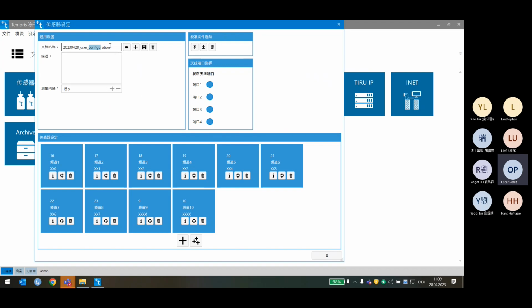It's very important to always configure the system with the sensors we are going to use. If we always use 10 sensors, we save once and only update this file every year after the recommended annual calibration. But if we decide tomorrow to use only 3 sensors, we strongly recommend configuring with only 3.